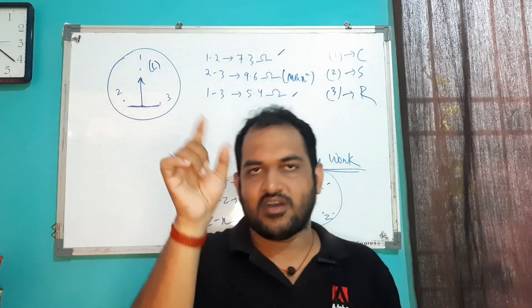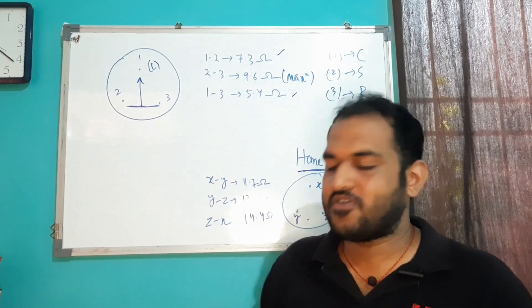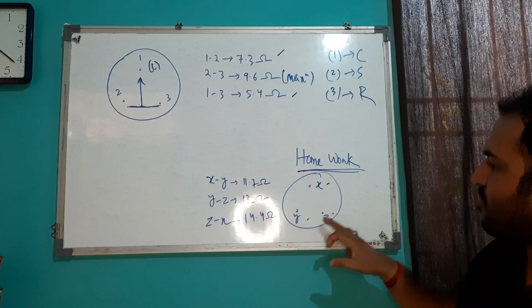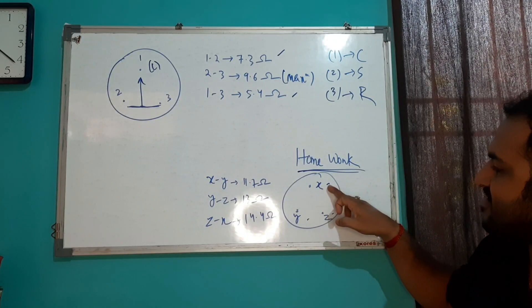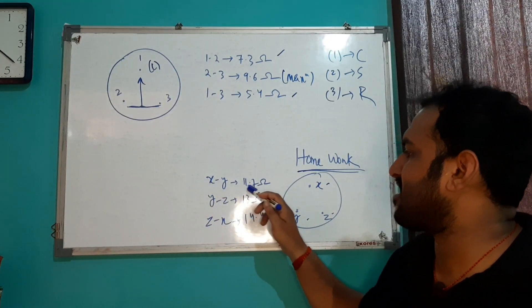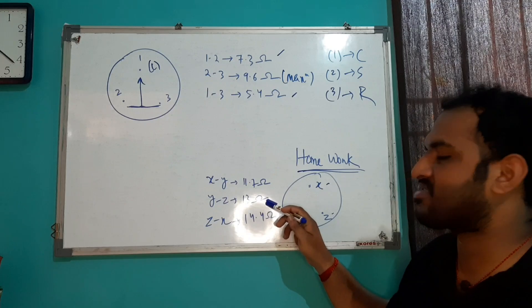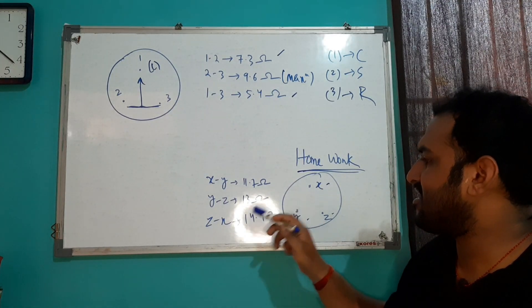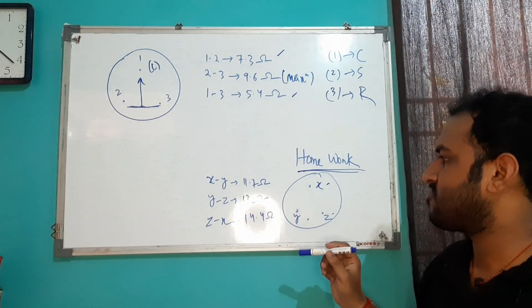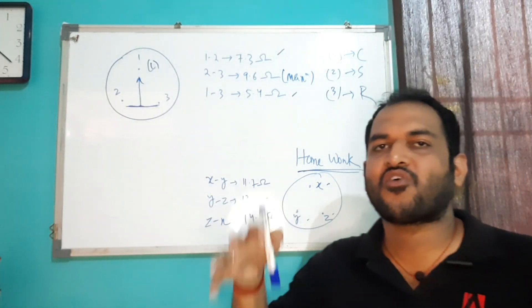You can identify all three terminals by this method using your multimeter. Here is a homework problem: a compressor has three terminals X, Y, Z. The resistance across X and Y is 11.7 ohms, resistance across Y and Z is 13 ohms, and resistance across X and Z is 14.4 ohms. Which one is your C, S, R terminal? Please write your answer in the comment section.